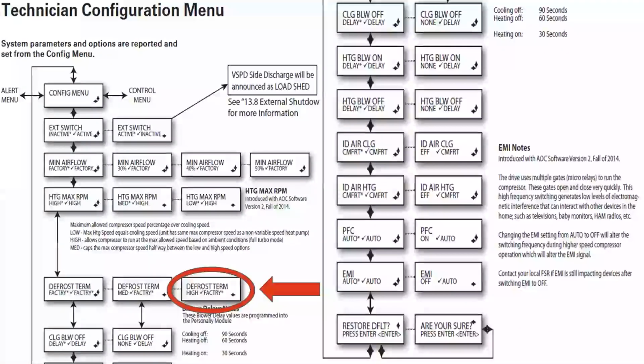Configuration menu. So again, we're pressing and holding the top and bottom button till it displays monitor. We've gone through alert history, and now we're at configuration menu. From configuration menu, we're going to scroll down. We have that external switch. I don't see too many people using it, but that's where we're going to access it if we have a generator relay connected. Minimum airflow.